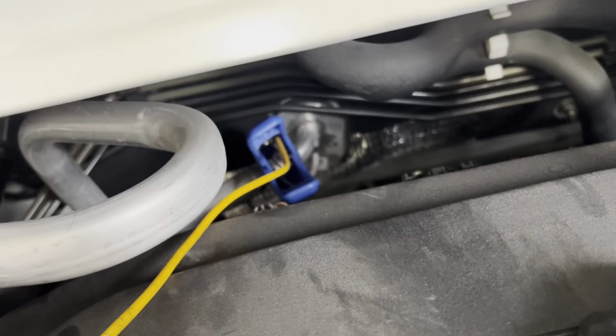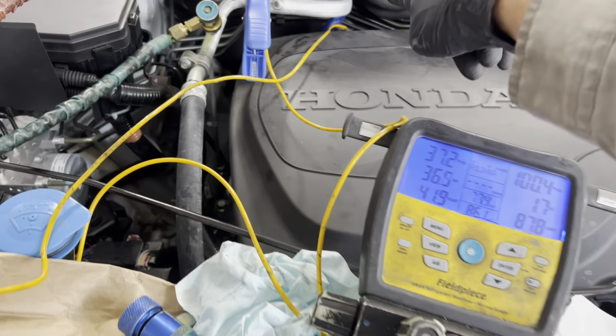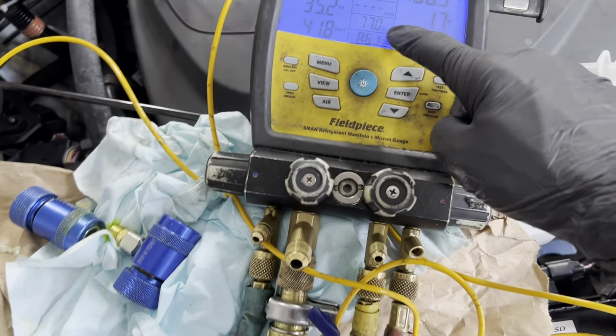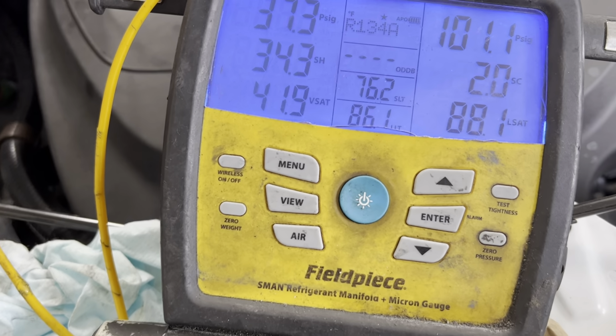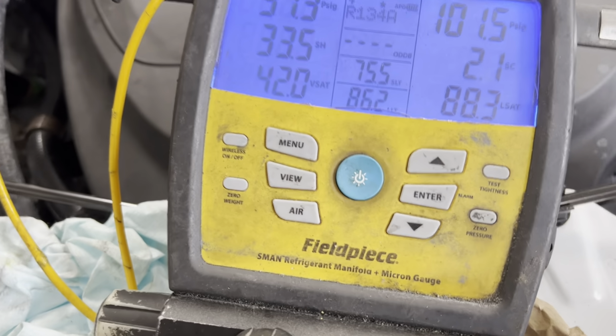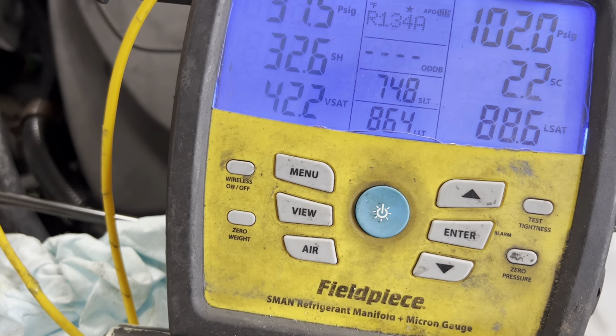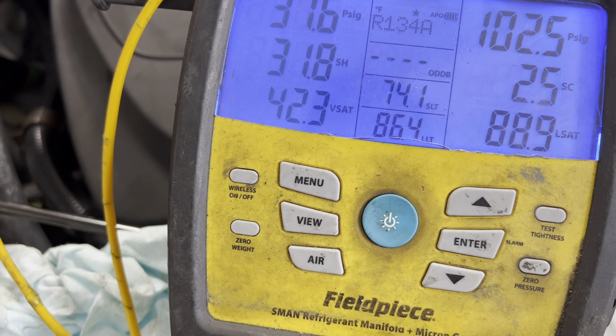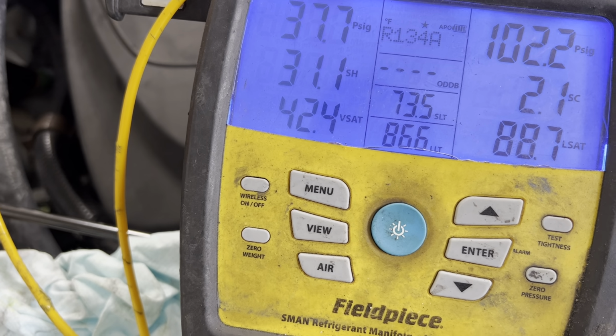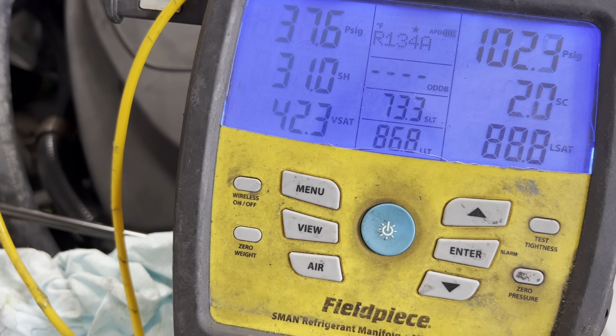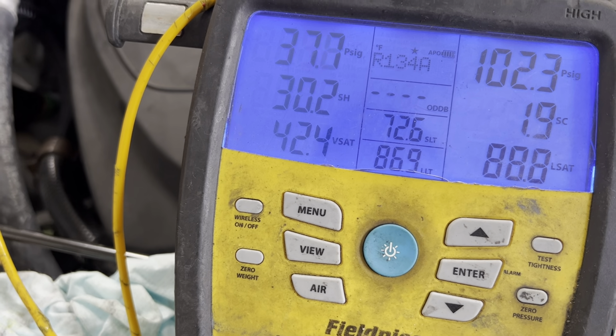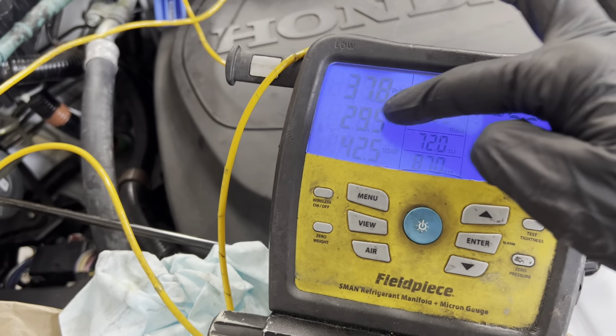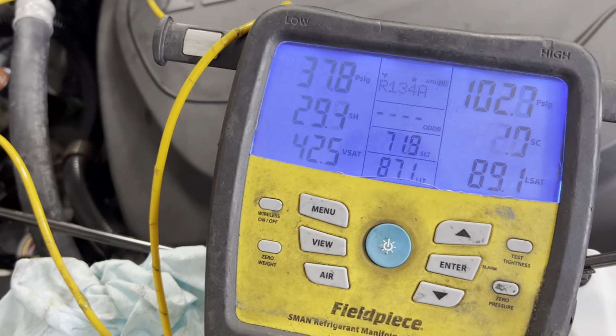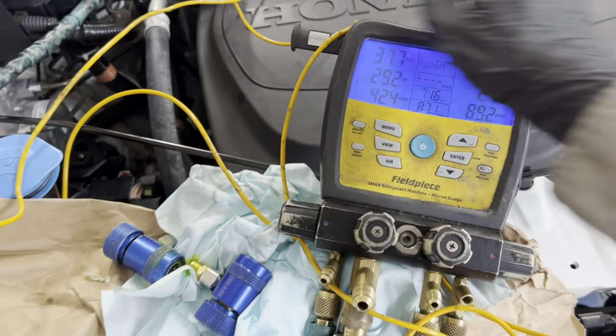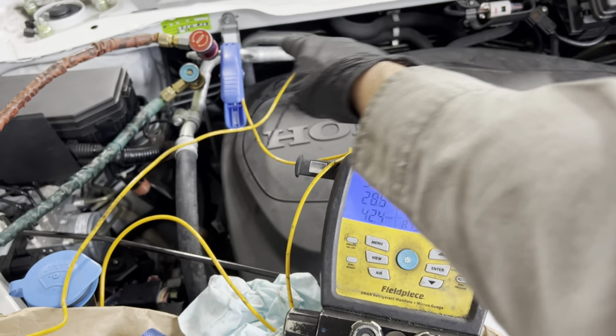Okay, so now I'm taking the temperature right out of the evaporator. You can see it dropping, and you'll see our superheat go down a little bit. Not a lot, it's going. And you can see suction line temperature and superheat slowly start to drop together because we're having all that added heat energy at this point because of the internal heat exchanger.